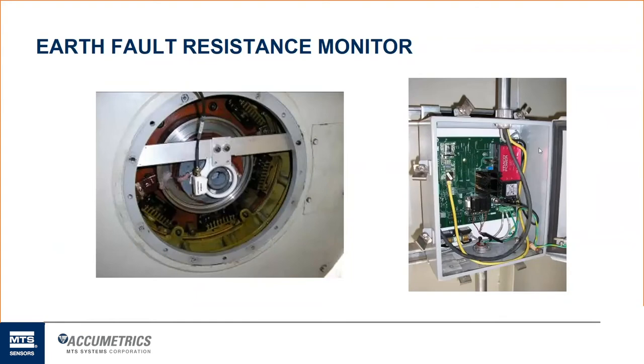To the right, you can see an example of a customer mounting our receiver on some Unistrut, which is usually what we would recommend. That would be something the end user would be responsible for. They would take care of the installation of our equipment. We would send this out ahead of time before their scheduled outage, and a lot of this can get done and mounted before we show up to do the installation and commissioning of the rotor mounted components.